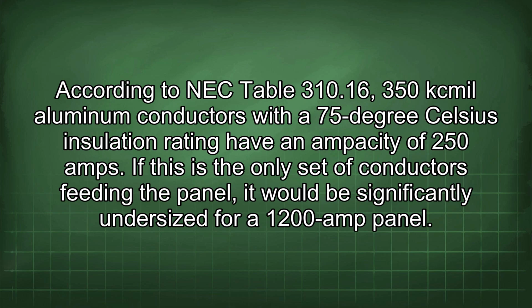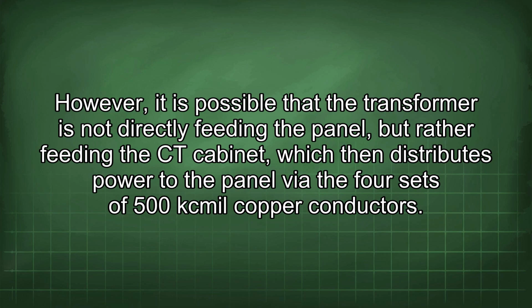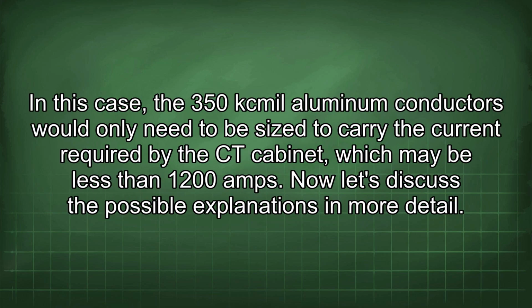According to NEC Table 310.16, 350 kcmil aluminum conductors with a 75 degrees Celsius insulation rating have an ampacity of 250 amps. If this is the only set of conductors feeding the panel, it would be significantly undersized for a 1200 amp panel. However, it is possible that the transformer is not directly feeding the panel, but rather feeding the CT cabinet, which then distributes power to the panel via the 4 sets of 500 kcmil copper conductors. In this case, the 350 kcmil aluminum conductors would only need to be sized to carry the current required by the CT cabinet, which may be less than 1200 amps.